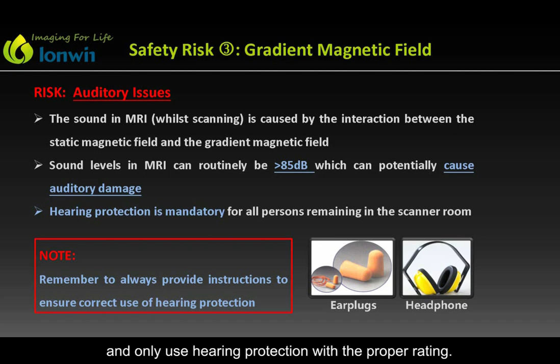The sounds vary between MRI sequences, and sound levels in MRI may routinely rise above 85 decibels. This is an important safety concern because prolonged exposure to such sound levels has been shown to cause hearing loss. MRI staff must prevent hearing damage caused by exposure to the acoustic noise of the MRI scanner. All persons remaining in the scanner room during scanning must be protected from hearing loss with appropriate hearing protection fitted correctly. Such hearing protection includes headphones or earplugs. Remember to provide instructions for appropriate use and only use hearing protection with the proper rating.